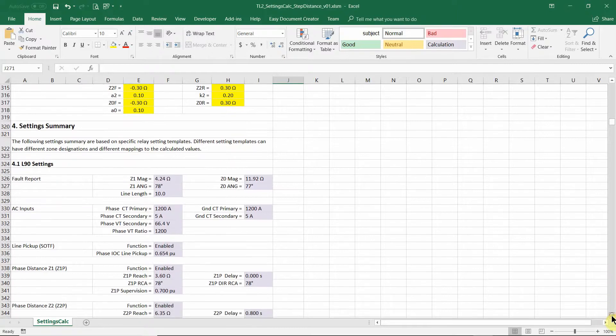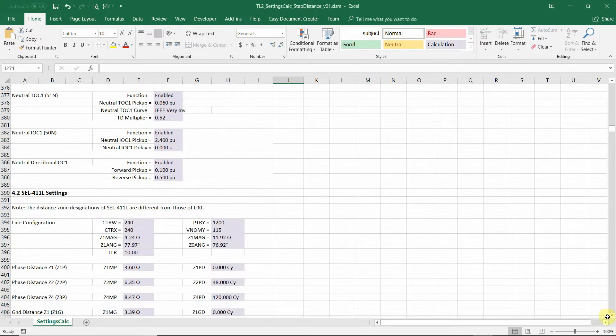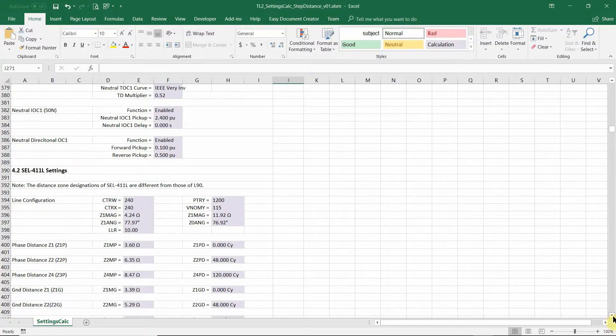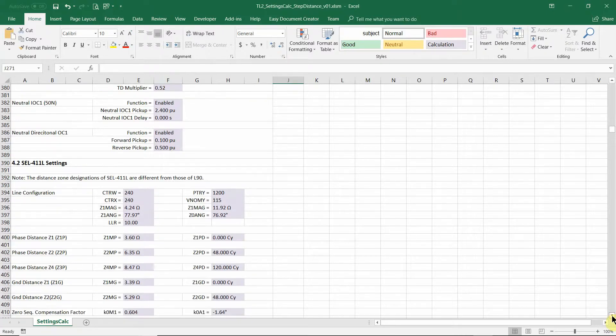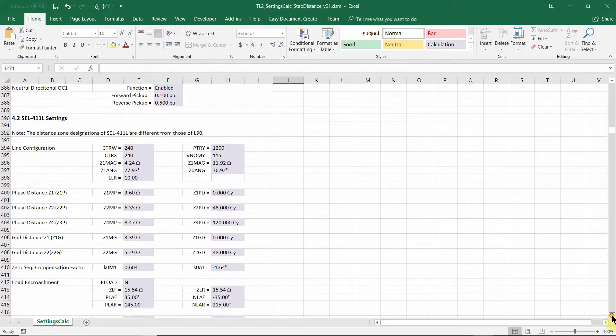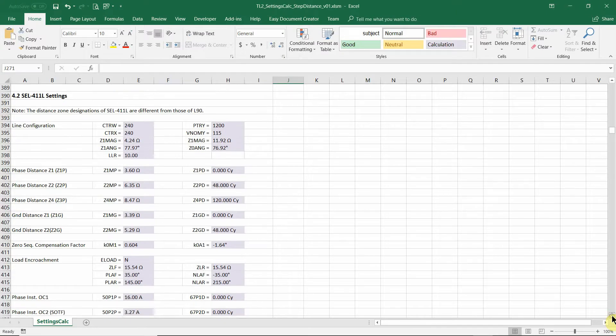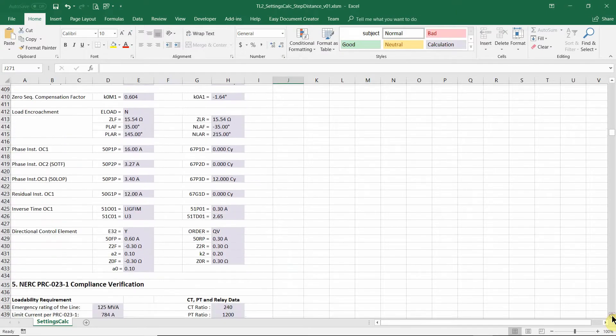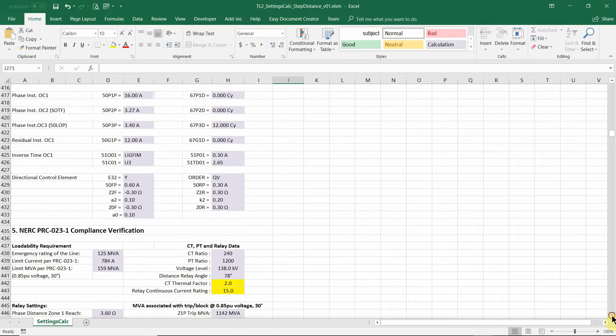So in section four of this document, there's setting summary for each relay. We know that GE relay, for example, they use PU for current settings. And the SCHWEITZER relay use AMP for current settings. So we have to make a translation from the general setting calculation to those individual relays.